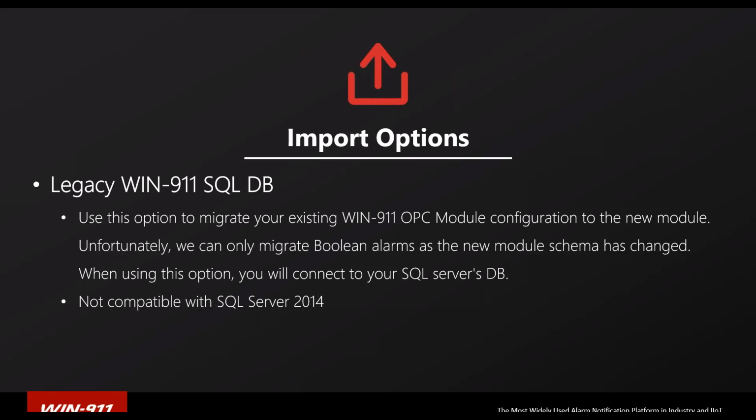And one of the downsides to this is that one of the functions we're using in SQL to make this possible is not supported in SQL Server 2014, as we found out toward the end here. What that means is if you have WIN-911 with databases in SQL Server 2014, it's not going to work. You can either take that database and move it to a newer SQL Server, or just update that SQL Server, which is easily done through the Microsoft SQL Server install. You just run it, click update, and point it to that instance, and then that installer will update it for you.